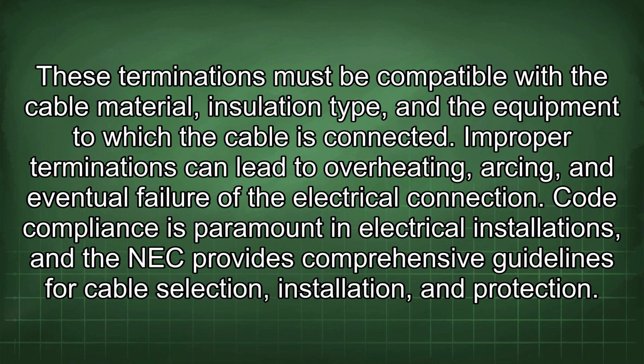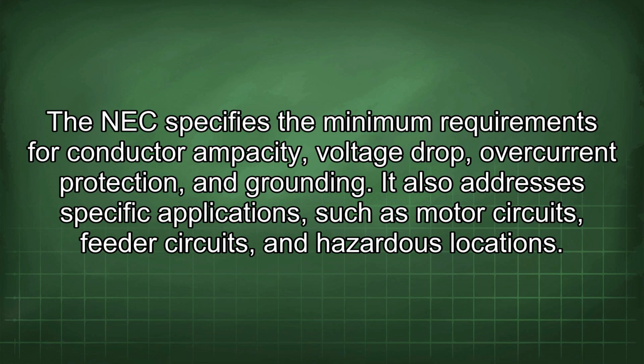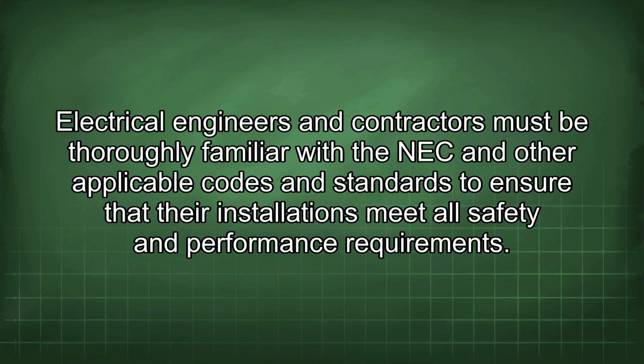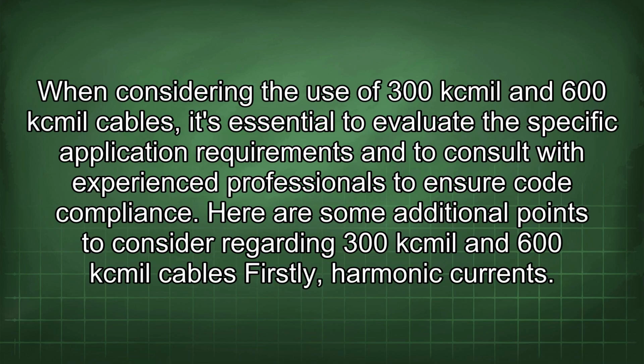Code compliance is paramount in electrical installations, and the NEC provides comprehensive guidelines for cable selection, installation, and protection. The NEC specifies the minimum requirements for conductor ampacity, voltage drop, overcurrent protection, and grounding. It also addresses specific applications such as motor circuits, feeder circuits, and hazardous locations. Electrical engineers and contractors must be thoroughly familiar with the NEC and other applicable codes and standards to ensure that their installations meet all safety and performance requirements. When considering the use of 300kcmil and 600kcmil cables, it's essential to evaluate the specific application requirements and to consult with experienced professionals to ensure code compliance.